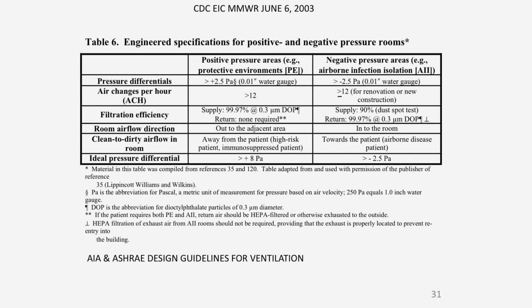So we look at slide 31 and see the infection control parameters: the pressure differentials for a pressurized protective environment, and the pressure differentials for the negatively pressurized airborne infection environment. And those pressures, again, are what's driving the air. The pressure is truly an infection prevention parameter because it controls where things move from a clean to dirty perspective. Always think of the patient as either clean or dirty, and clean to dirty airflow is what we want. And the air change rates, which we'll talk about very shortly, are an essential part of that pollution management, if you will.